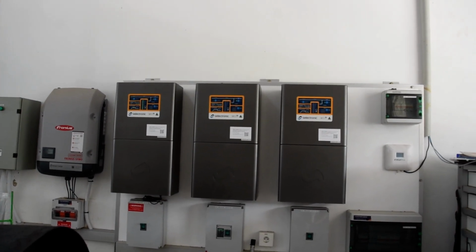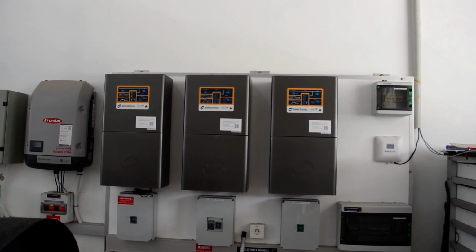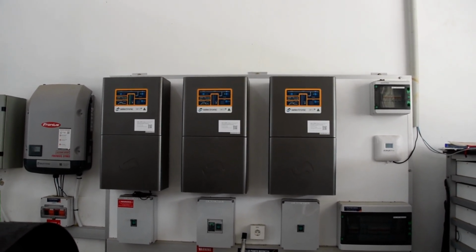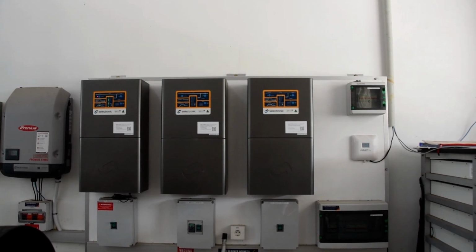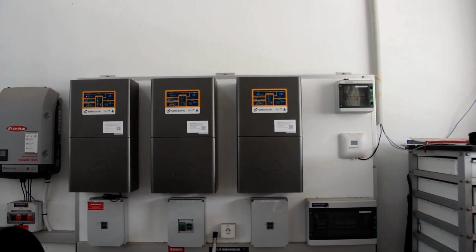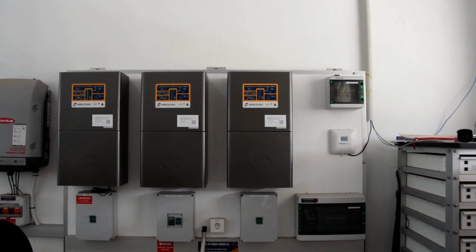So what I'm looking at is over at the house, way over there, if we go below 25% state of charge, imports from here. If this thing gets down to 25% state of charge, it's not going to export anymore, and it's going to want to try and import. So I can do a limited number of imports during the night before it's going to need to run the genset, which I can't do automatically. I'm going to have to do it manually. So what I've been doing is managing the load so that we don't hit that situation by carefully monitoring whether the breaker for the PLN has tripped by itself. That hasn't done it for a week. I don't know why this last week's been different, but it's worked perfectly, and consequently the household system has not even had to do an import from this overnight.